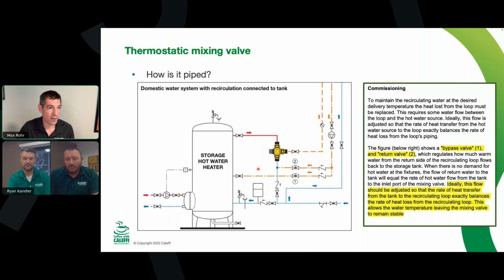Same thing, pre-occupancy is really the best way to do this, with only the recirc pump going. That's what we want to do to make sure we're getting this right. If we have a bunch of fixtures on, it's going to change the heat loss out in the building. So pretend this is hydronic baseboard, and we want to figure out what the delta T is here, and that's going to help us adjust it.